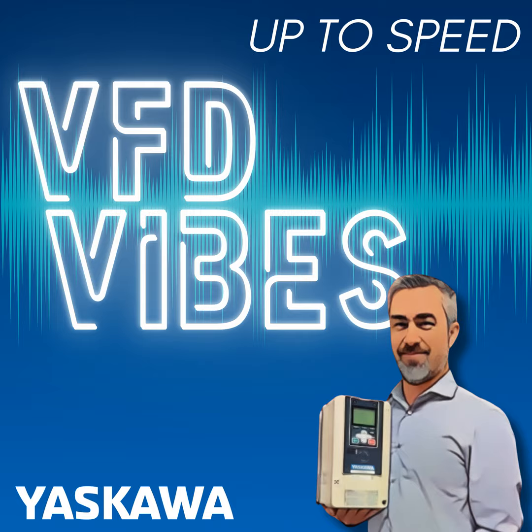These modules have built-in thermistors so that your drive can actually tell you how hot it is. Most drives will show that temperature on the keypad or through your network connection if you are using the data registers and connecting your drive to a PLC or SCADA or intelligent supervisory system. But remember, drives can't cool below ambient temperature. Managing your environment is step one in preventative care.